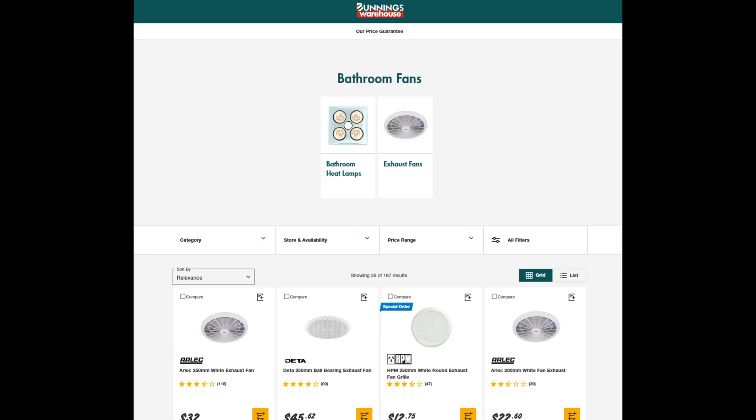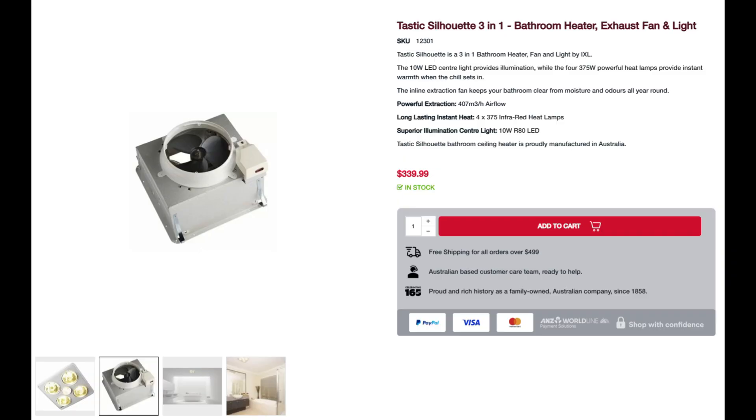In the old days you'd go to Bunnings, get an iXL bathroom fan or any sort of fan, cut a hole, install it in your ceiling, get an electrician to wire it up and Bob's your uncle. But that configuration does not comply. Most people going to somewhere like Bunnings to buy that fan can easily get unstuck, because you only get the fan — you don't get the duct or the roof vent that will expel the air out into open air. So you've only got half the system.